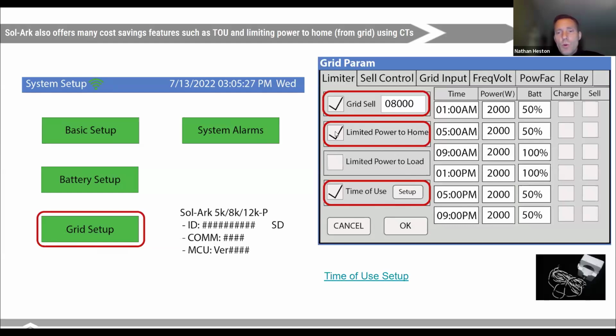Limited power to home will use the CTs that come with the inverter. I'm showing those in the bottom right corner. Limited power to the home is going to limit how much overall power you pull from the grid. You can use batteries to supplement the power being pulled from the grid so you don't exceed a certain value, which can be nice for avoiding things like peak demand charges. You could also do limited power to the load. If you're only backing up part of the home, this can be useful.